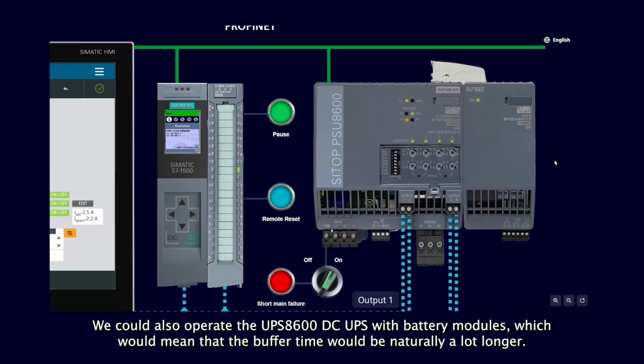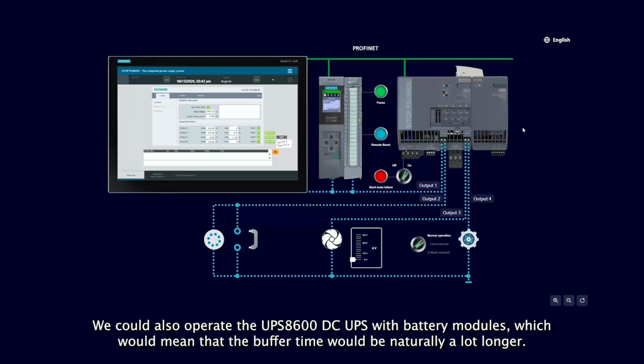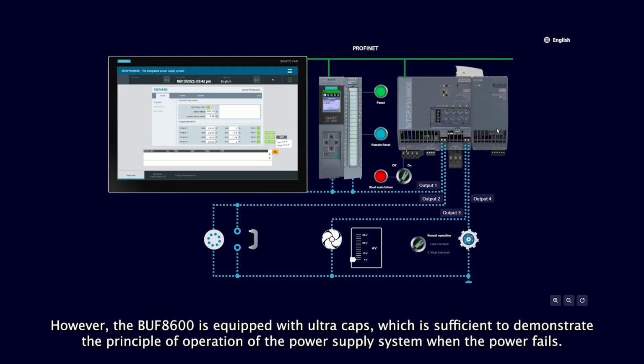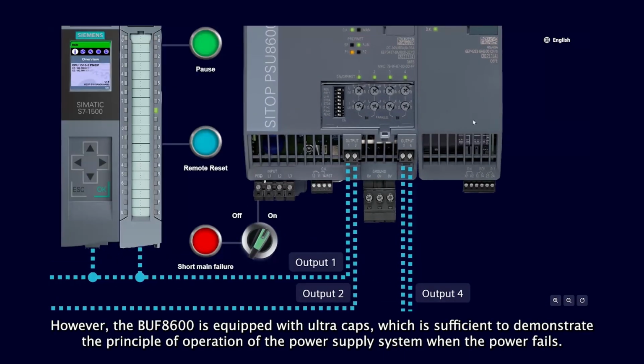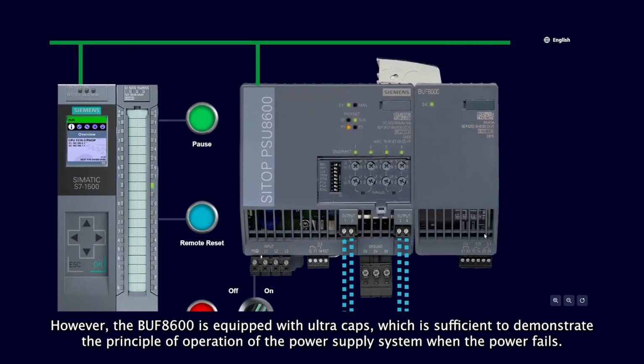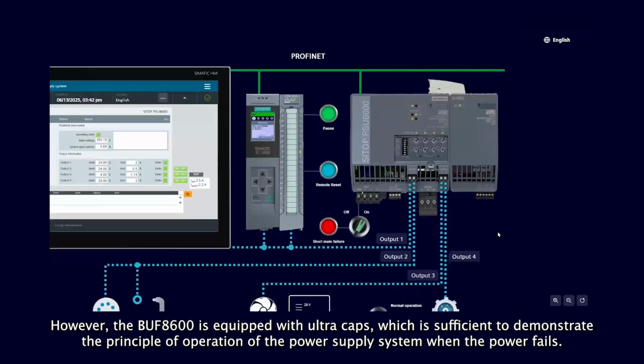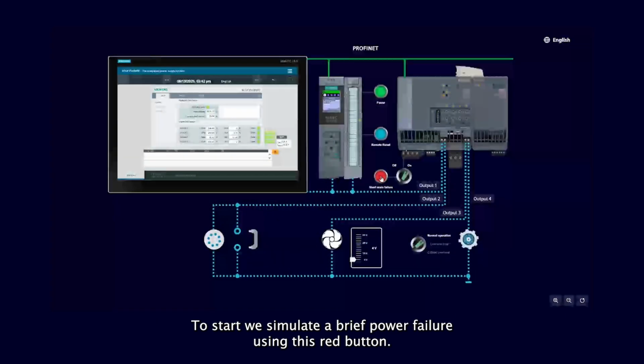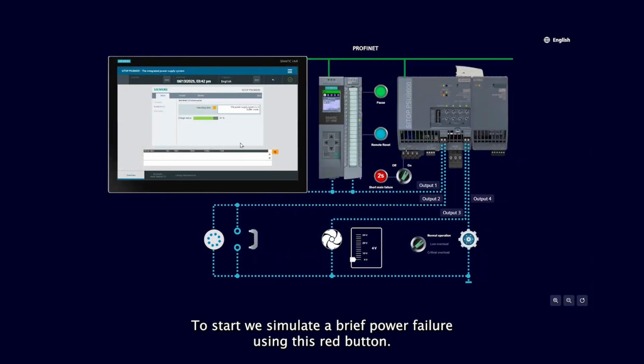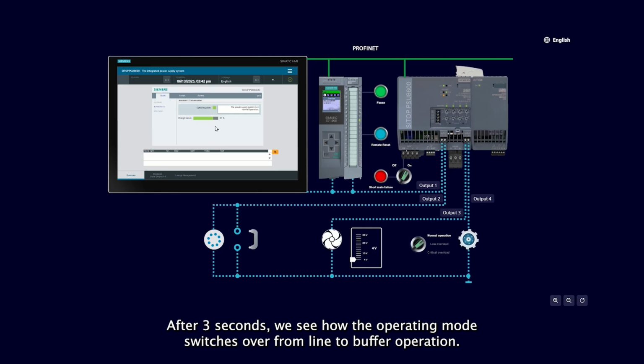We could also operate the UPS 8600 DC UPS with battery modules, which would mean that the buffer time would naturally be a lot longer. However, the BUF 8600 is equipped with ultra caps, which is sufficient to demonstrate the principle of operation of the power supply system when the power fails. To start, we simulate a brief power failure using this red button. After 3 seconds, we see how the operating mode switches over from line to buffer operation.